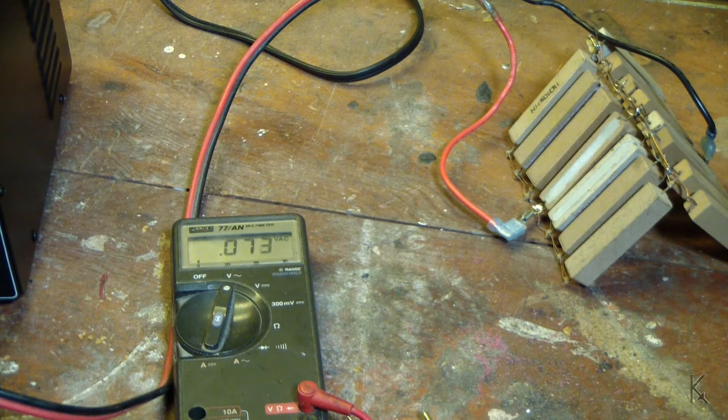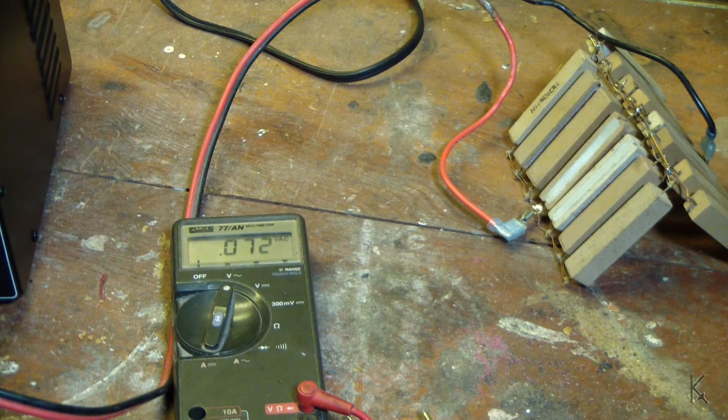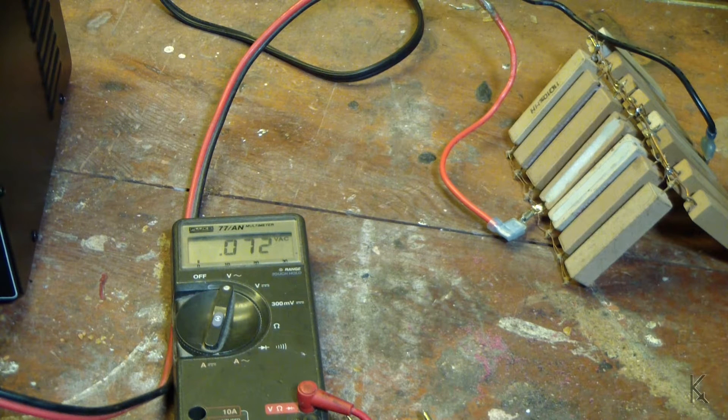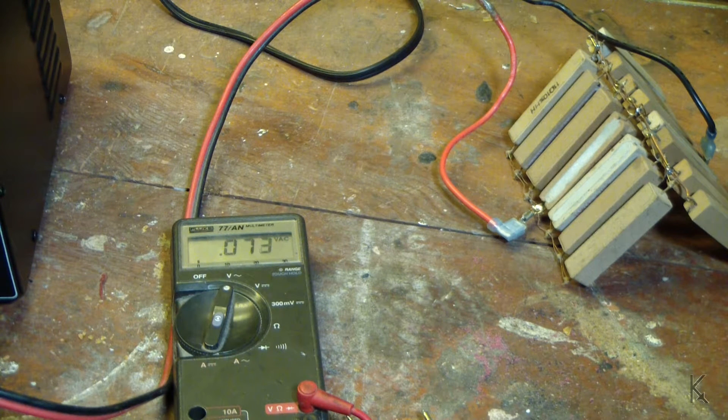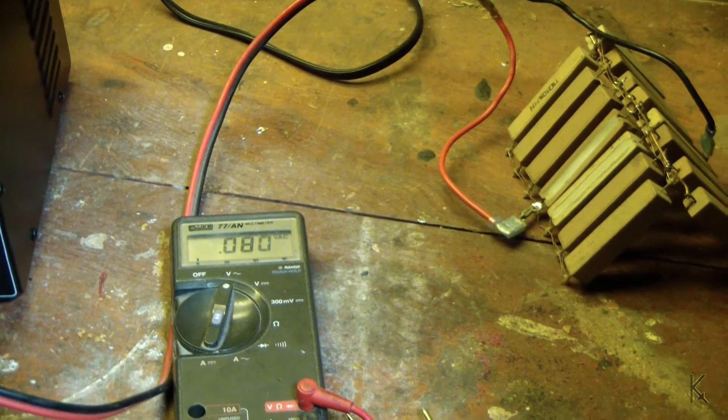The problem is, without the chassis of the power supply being grounded, you end up with a transient voltage on the chassis. Now, since it's coming through small capacitors, not enough to shock you, but certainly a potential. Let me demonstrate.